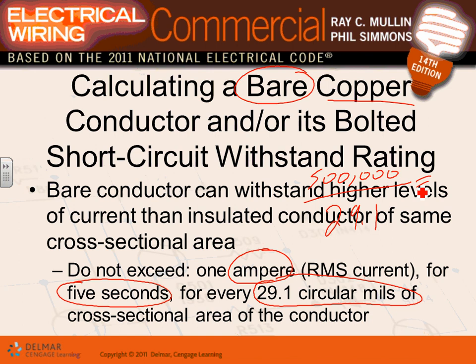If it's an insulated conductor, the value that they use is 26 something. 26. Same thing, 1 amp for 5 seconds for 26 circular mils. So if it's insulated, you divide by 26. That's called the withstand rating of conductors, the withstand rating of conductors.